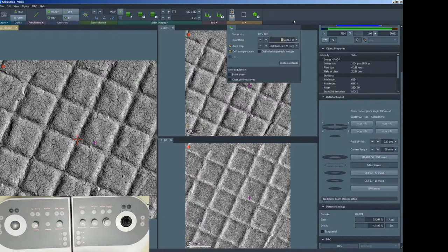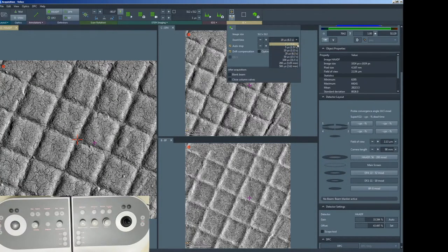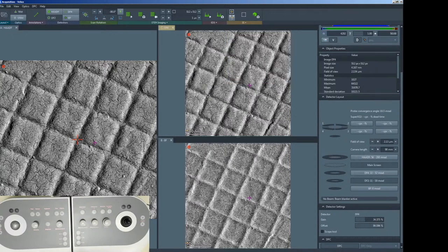But once you have a compromise between the magnification and the sample drifting, then you also want to maximize this dwell time. There's no exactly right or wrong setting. It just depends on the magnification. Like right now we are at relatively low mag.